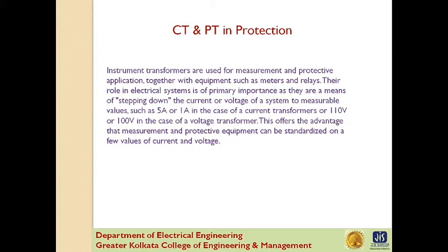This transformer steps down the voltage to a safe limit value which can be measured by the ordinary low voltage instrument like a voltmeter, wattmeter or watt-hour meter. Now the current transformer along with the voltage transformer are instrument transformers. Instrument transformers scale the large values of voltage or current to small and standardized values that are easy to handle for the measuring instrument and protective relay. The instrument transformer isolates measurement or protection circuit from the high voltage of the primary system.